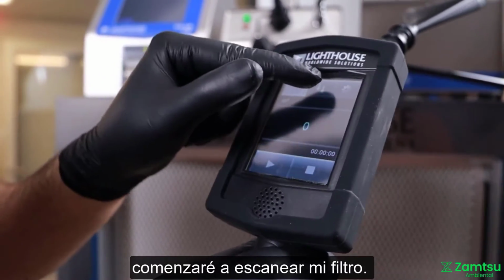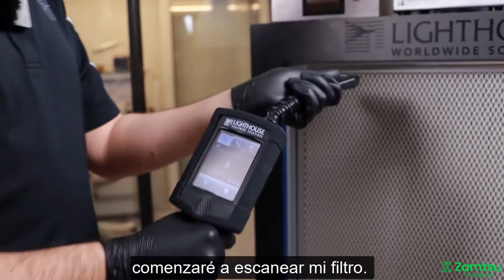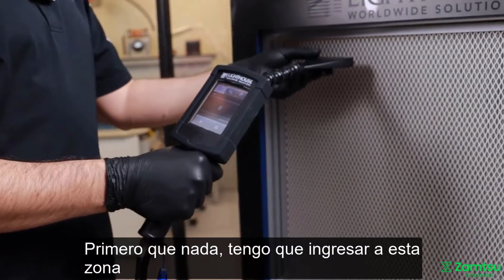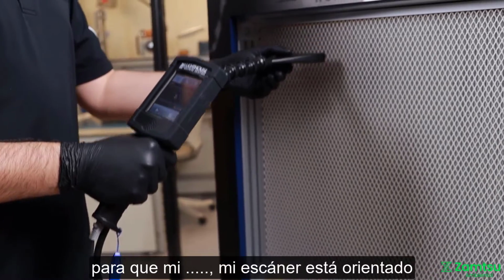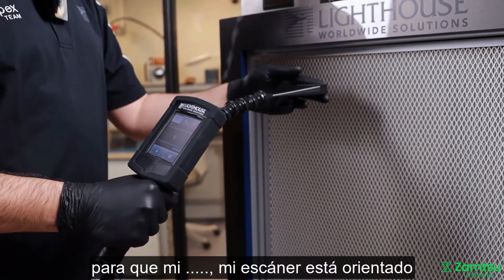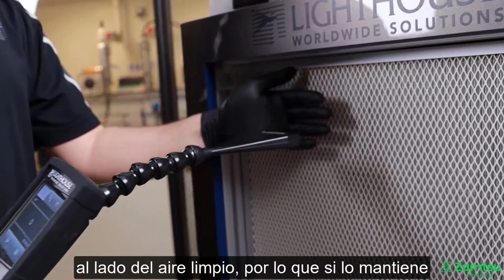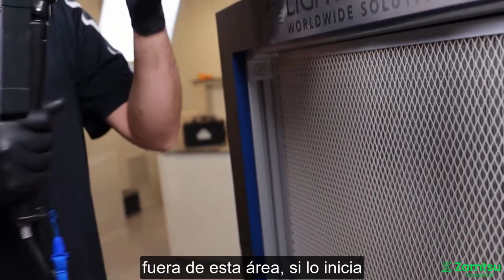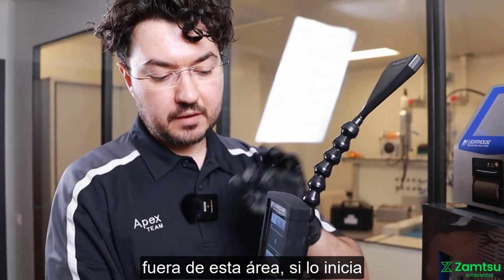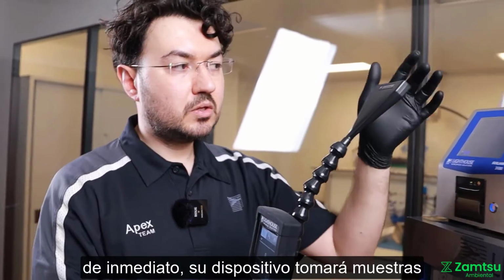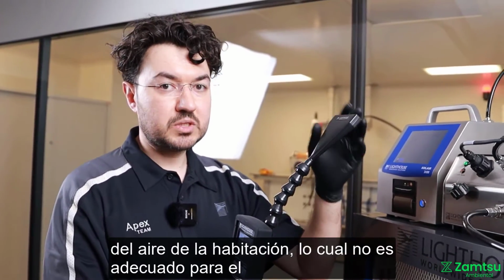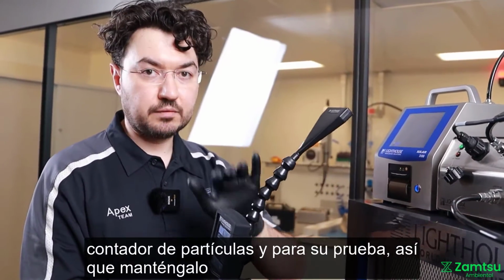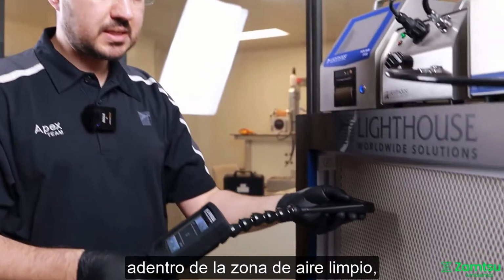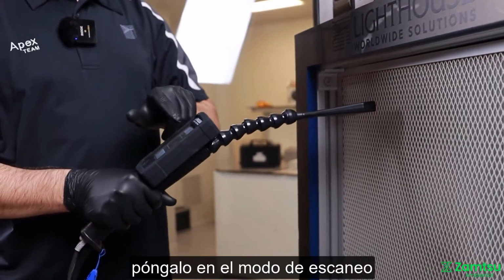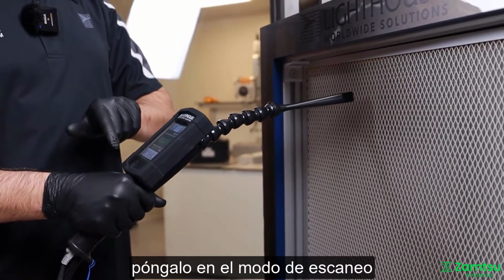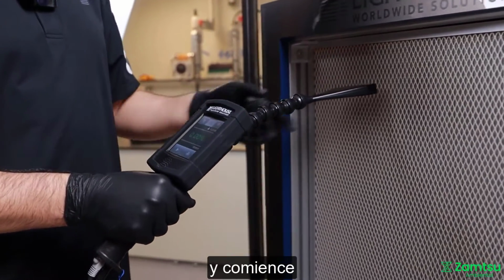So I'll start scanning my filter. First of all, I have to enter into this zone so that my scanner is open to the clean air side. If you keep it outside of this area and start right away, your device will sample room air, which is not okay for the particle counter and for your test. So keep it inside in the clean air, put it into the scan mode, and start.